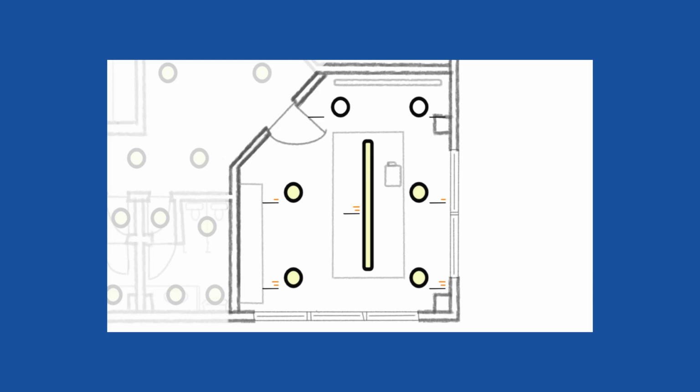The lights around the edge of the room, we'll drop them to a low level, so people can still see to move around the room if they need, but it's not so bright that it distracts from what's being projected. And the lights over the table will be a little brighter so people can read or take notes while the projector is being used. Like groups, there are 16 DALI scenes available for every DALI line, and the DALI devices can be a member of as few or as many DALI scenes as required.